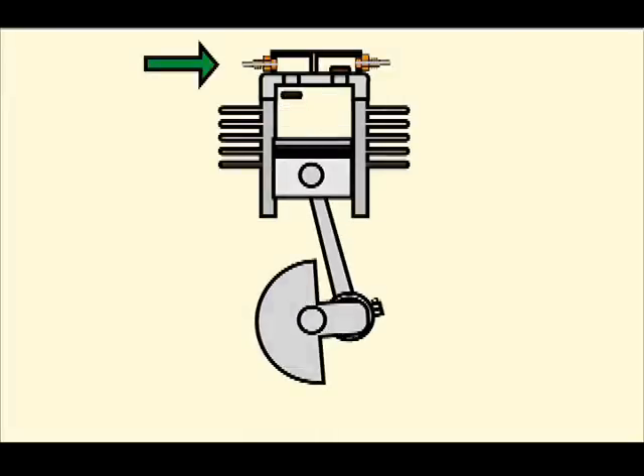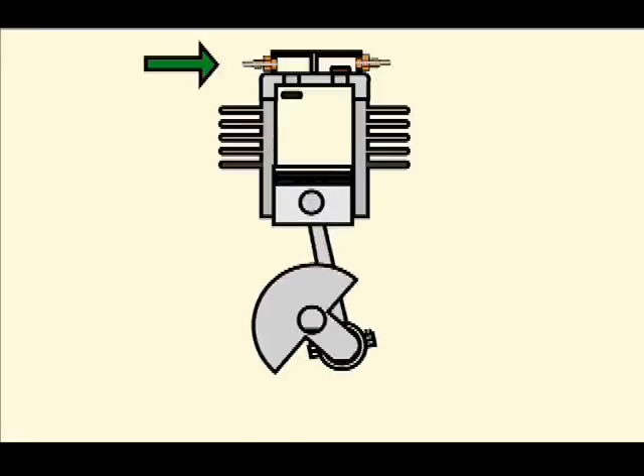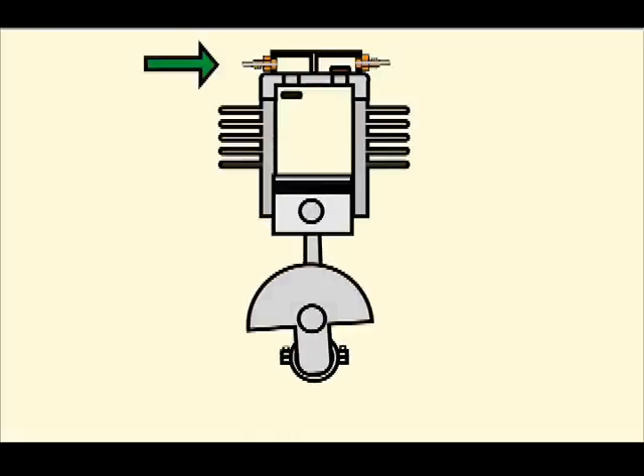Firstly, the compressor piston begins to move downward into the cylinder. This creates a partial vacuum and the atmospheric pressure opens the inlet valve, shown here in green. As the piston goes down, the cylinder is filled with atmospheric air. This results in an entire cylinder filled with air at ambient pressure.